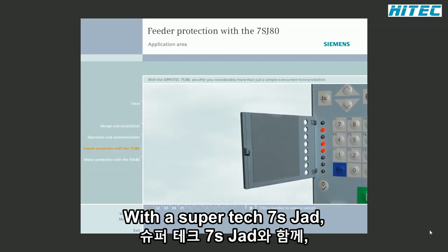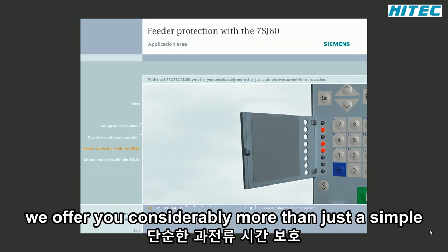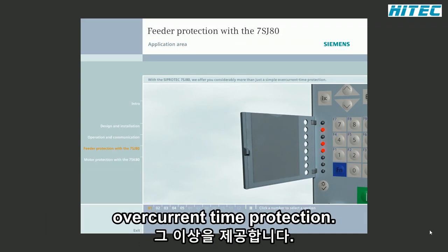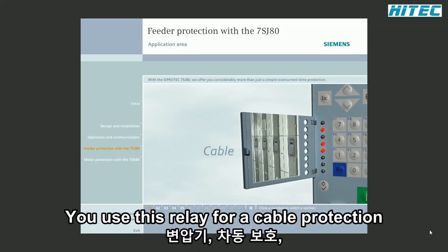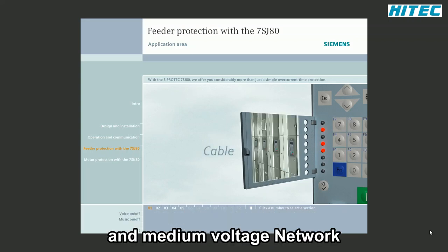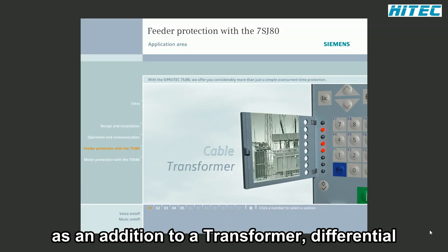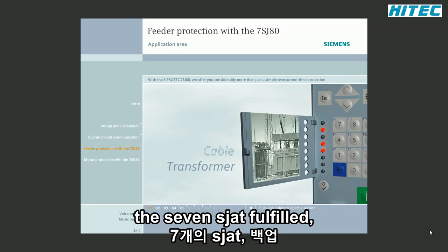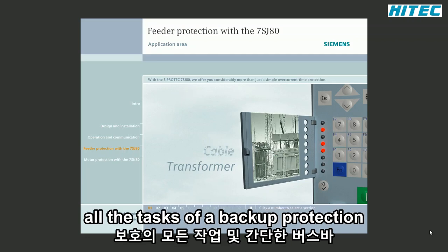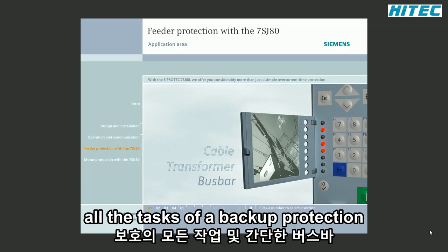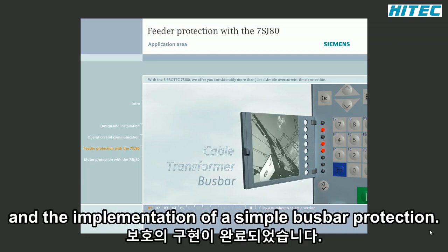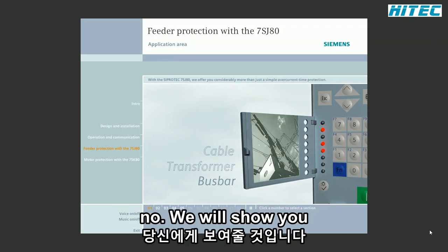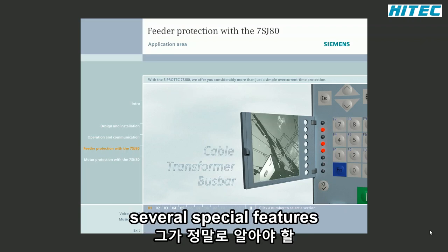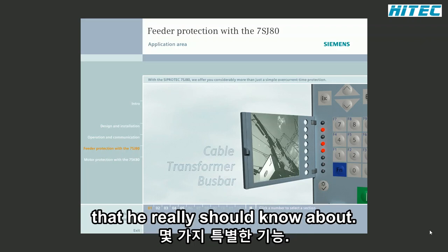With the SIPROTEC 7SJ80, we offer you considerably more than just a simple overcurrent time protection. You use this relay for cable protection in medium voltage networks. As an addition to a transformer differential protection, the 7SJ80 fulfills all the tasks of a backup protection. And the implementation of a simple busbar protection is also no problem. In the following, we will show you several special features that you really should know about.